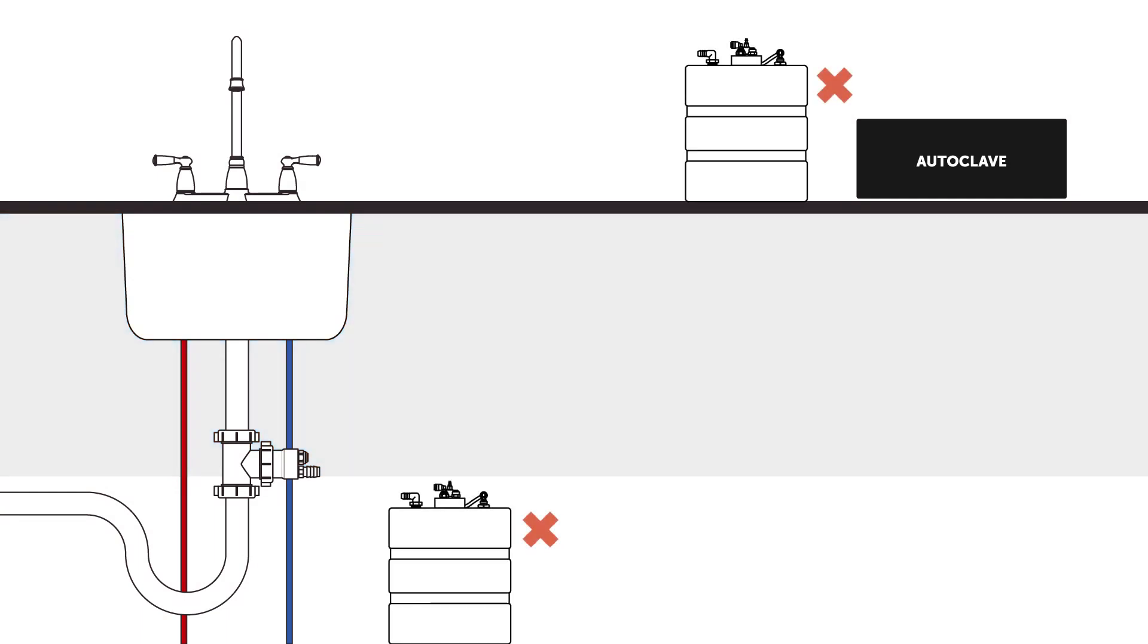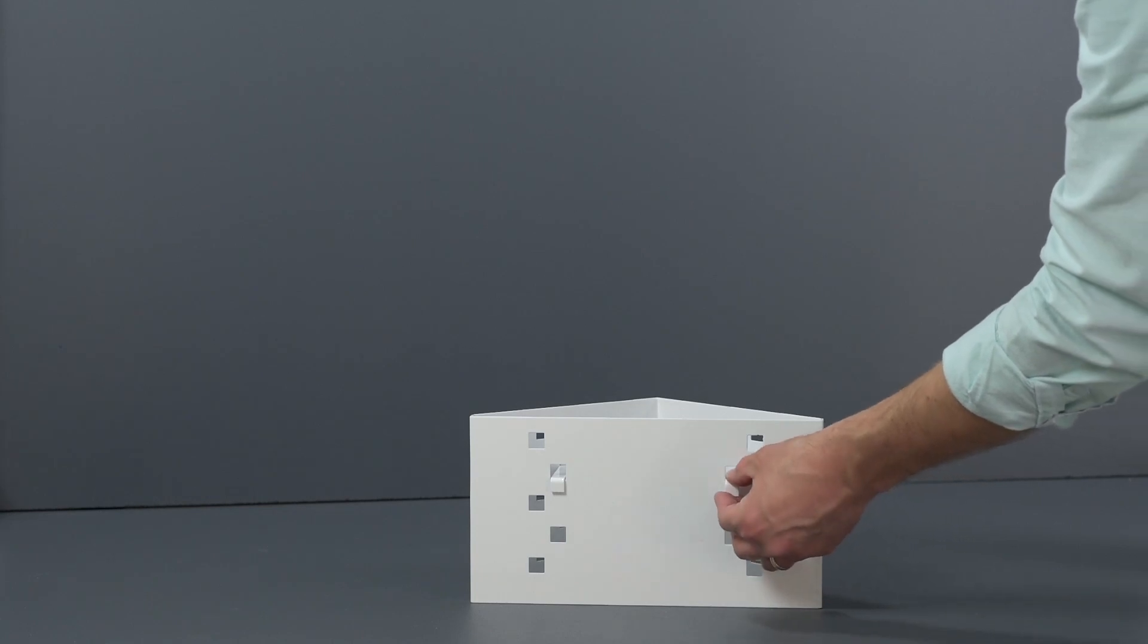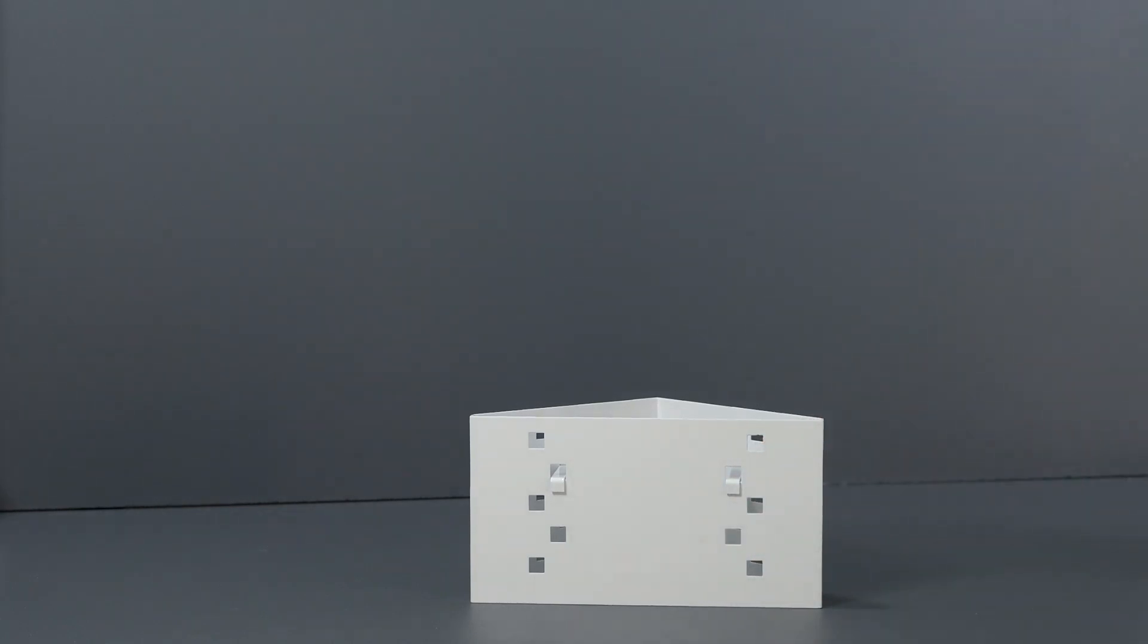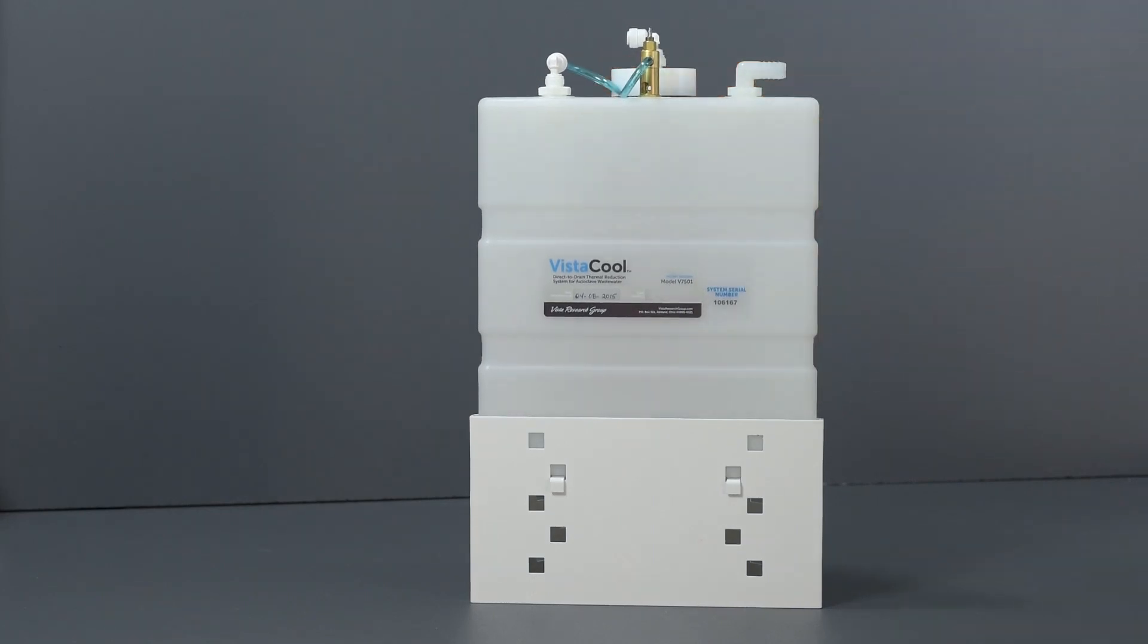Installing a tank at the wrong height may create resistance for proper water flow since the system is designed to take advantage of gravity flow. Adjustable tank stands for installing the VistaCool at the correct height are available as accessories when needed. These stands raise the tank height between half to 5 inches in half inch increments.